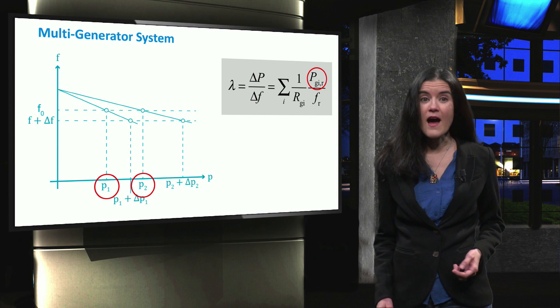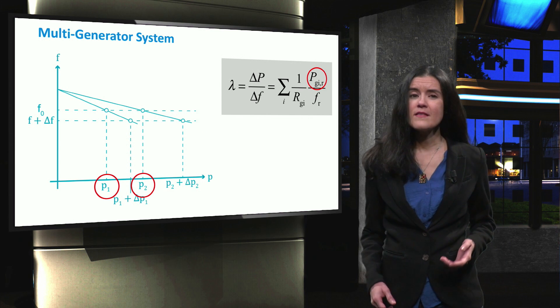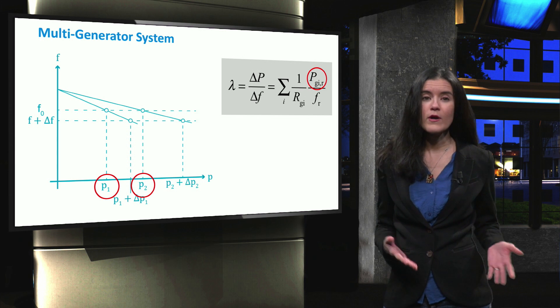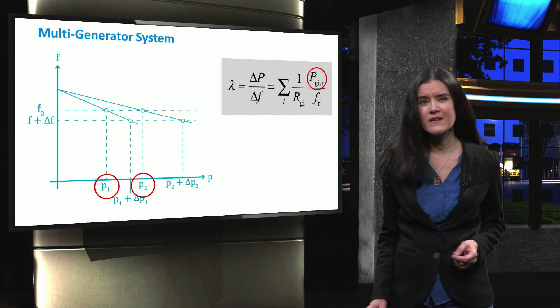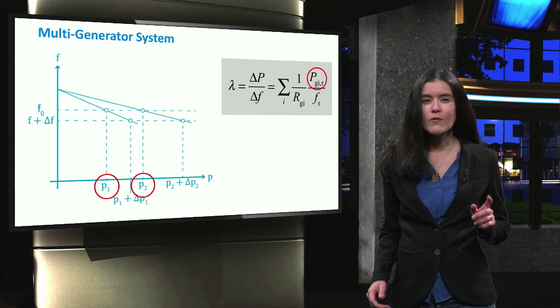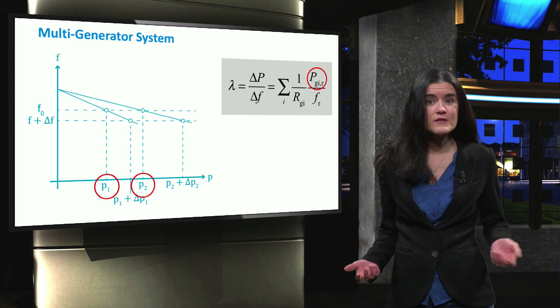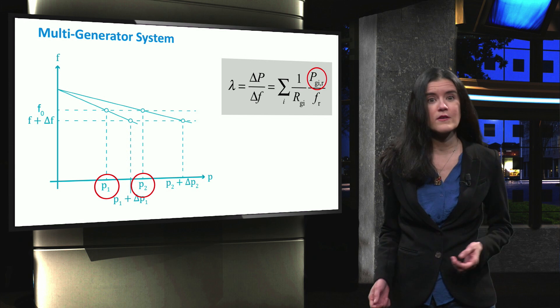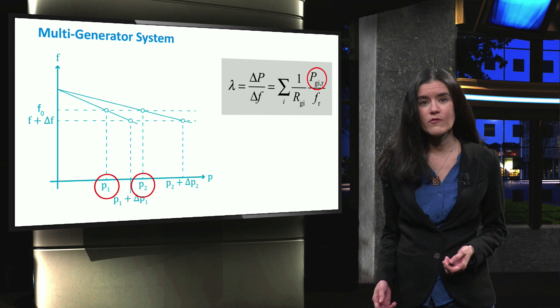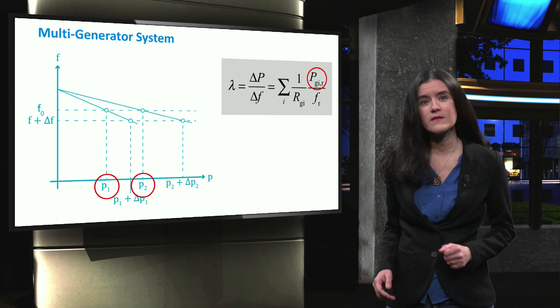It is important to note that after primary control takes place, the power balance is restored at a lower or higher frequency, which is not a desirable operation condition. We want to re-establish the frequency as close as possible to 50 or 60 Hz to avoid damages to equipment and loads, but that is done with a different mechanism.